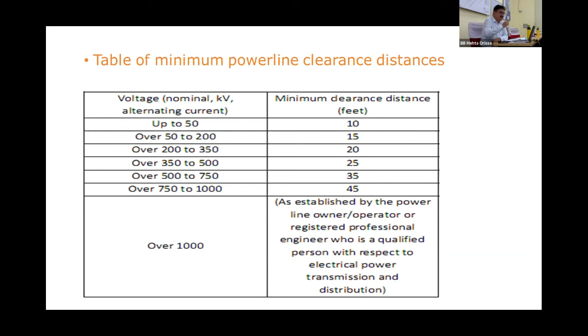The equipment design should have enough length to keep the person on the job at a safe distance from the live object. The tools used for this include hot sticks, sectionalizer clips, insulated links to extend reach, receive hooks, and discharge hooks, which are important because once equal potential is established, it has to be discharged afterward. There are also insulated hand tools like cutter sticks, clamp sticks, and shotgun sticks.